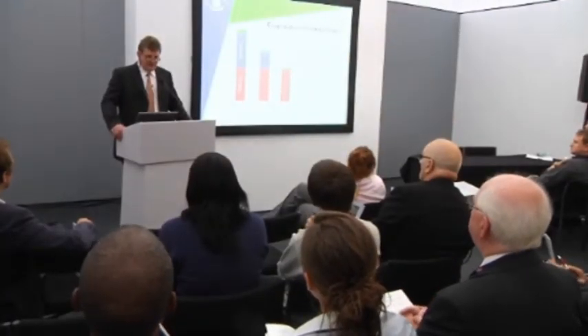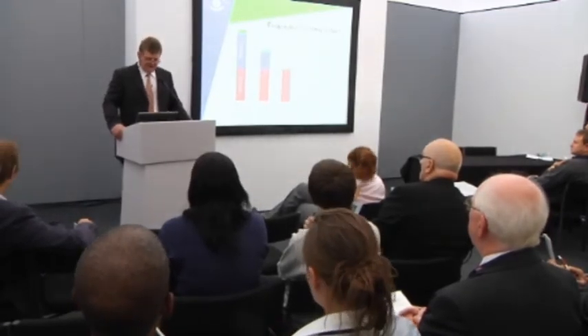If we use a ventilation system and evaporative cooling instead of refrigeration, it is technically possible to achieve a PUE of 1.1. That's an incredible level of saving — in some cases it looks too good to be true — but what I'll try to explain over the next few minutes is how we really achieve that using simple engineering in a simple modular system designed specifically for the IT sector.